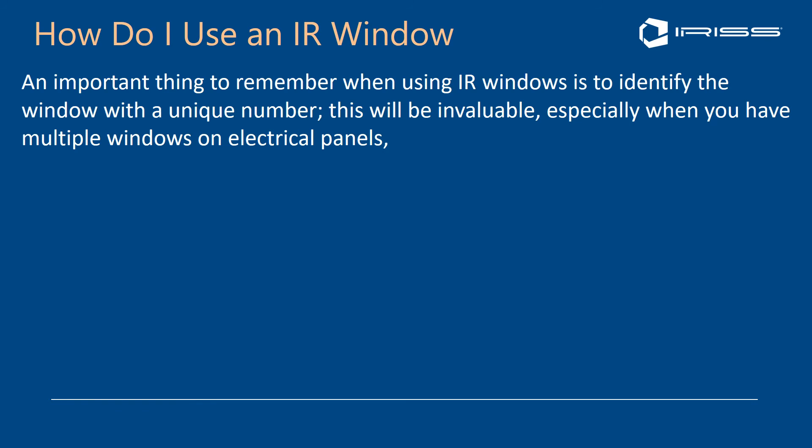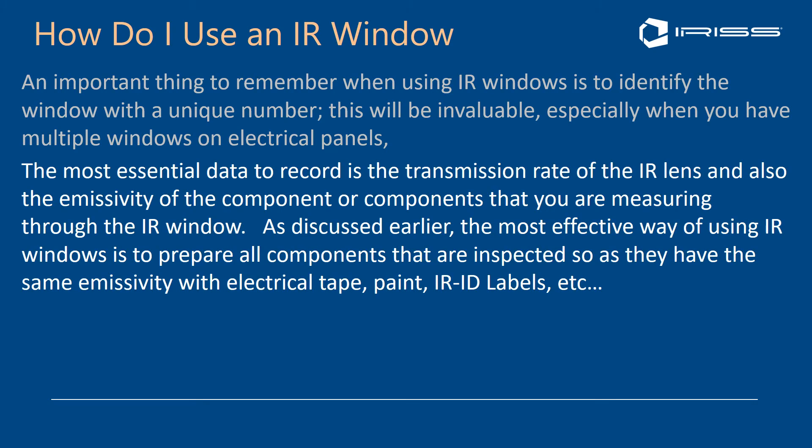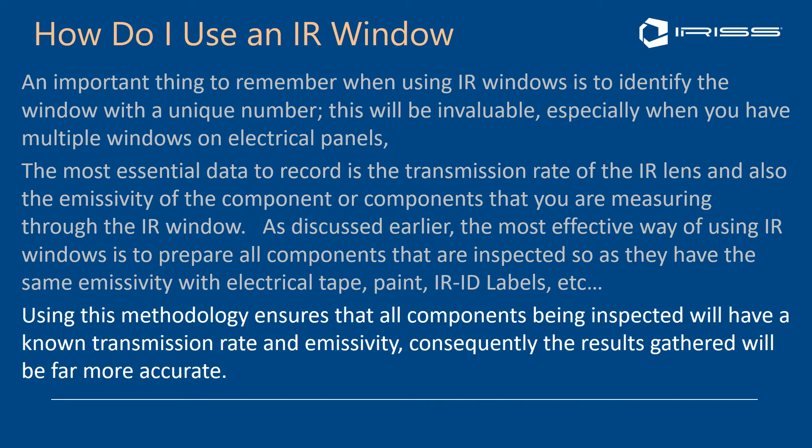An important thing to remember about infrared windows is that the identification of the window system itself should have a unique number — this is invaluable when you have multiple windows on multiple electrical panels. The most essential data to record is the transmission rate from the infrared lens, as well as the emissivity of the components you want to inspect. The most effective way of using an infrared window is to prepare all inspected components with the same emissivity using electrical tape. This ensures all components have a known transmission rate and known emissivity, making inspection results far more accurate.